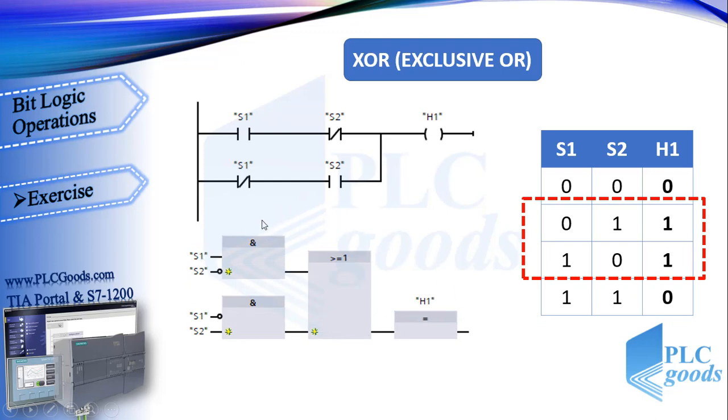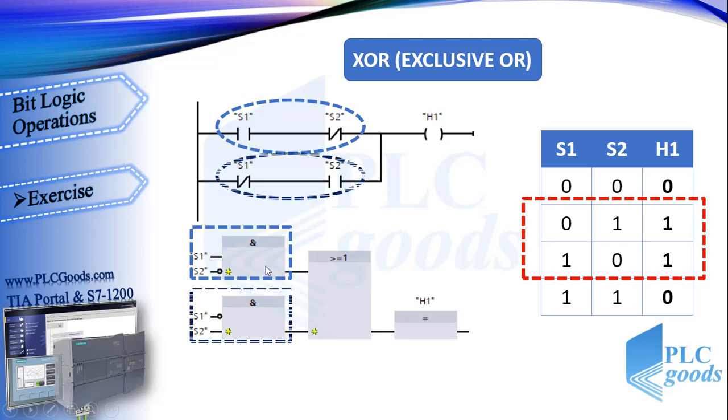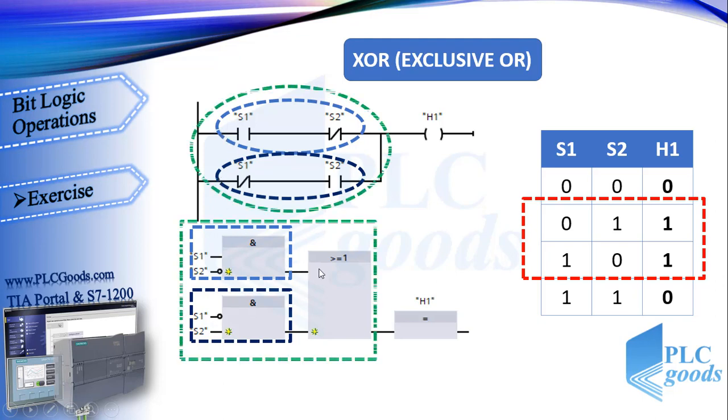In the first line of ladder program, S1 which is a normally open contact and S2 which is a normally closed contact are arranged in series. So S1 and S2 make an AND logic. As you see, inputs of this AND block are S1 and inverted S2. Similarly, the second line in ladder program and second AND block say the same thing. As you know, in ladder language with parallel branches, we have OR logic. Thus we have an OR block in bottom respectively. Finally both of them store the result of logic or RLO in H1.